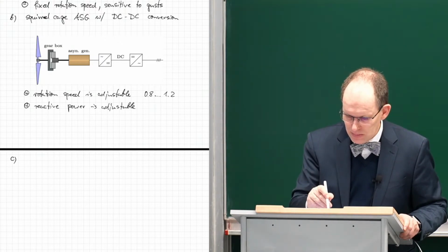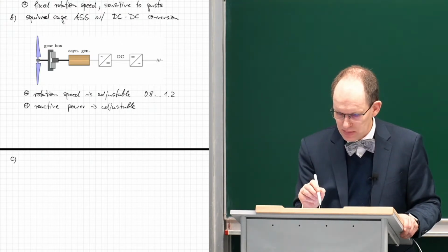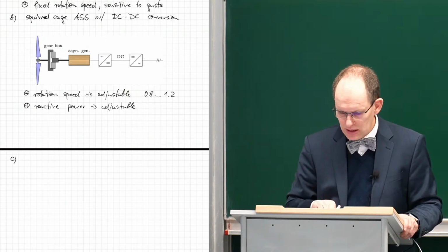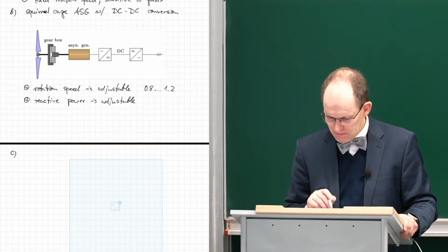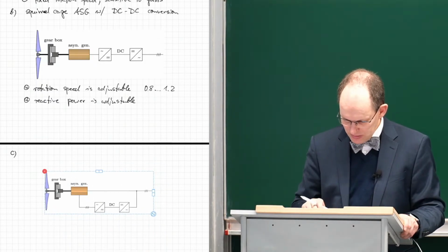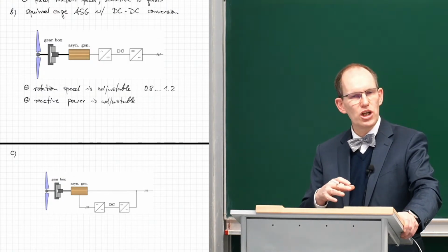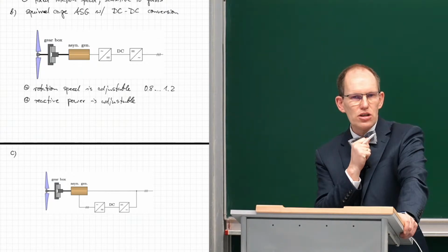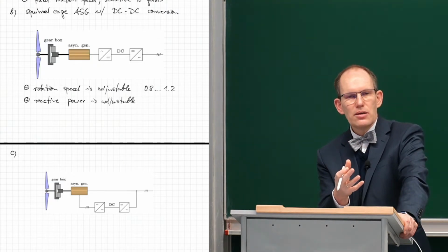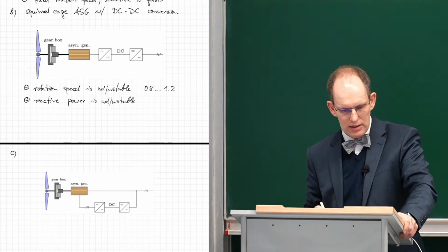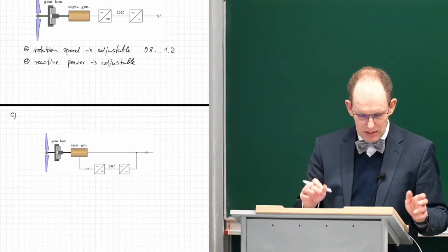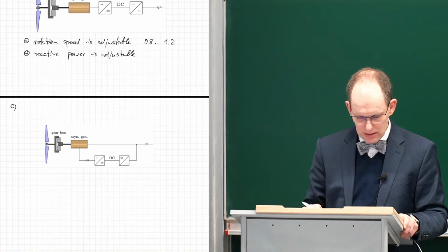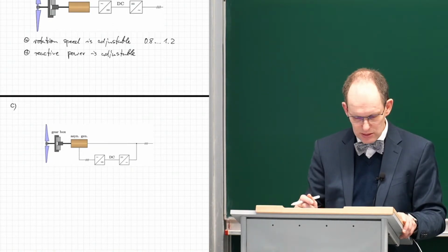So, and what is done is actually something like this here. The power that you generate, so you use the electricity that's generated in the squirrel cage, you use some of that, right? And this is then called variable slip control, and can either be done by adjusting the resistance in the squirrel cage.